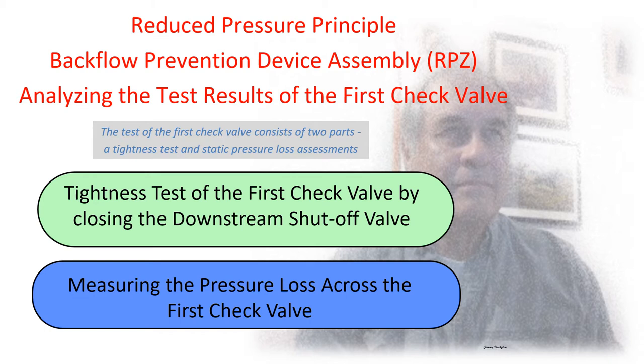The test of the first check valve consists of two parts: a tightness test and a static pressure loss assessment. The tightness test is conducted by closing the downstream shutoff valve. The static pressure loss is conducted by measuring the differential pressure across the first check valve.